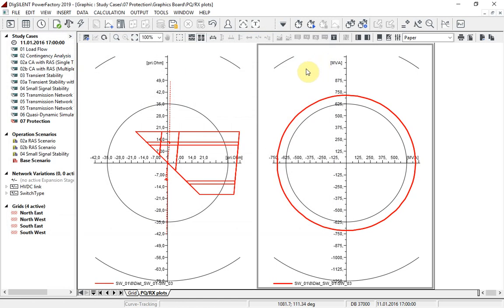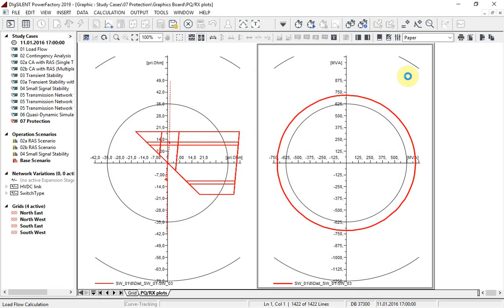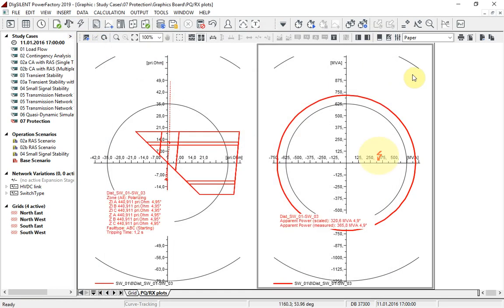If we run a load flow, we see that the current operation point is inside the characteristic, so the protection device will not operate. This is useful for grid operators to identify the operation point of generation groups, or power limits of transmission lines, in order to avoid nuisance tripping.